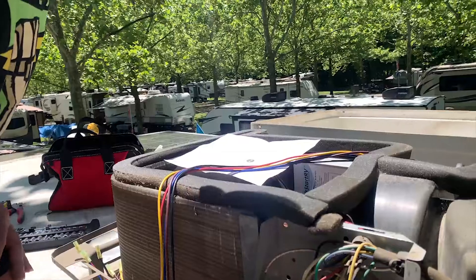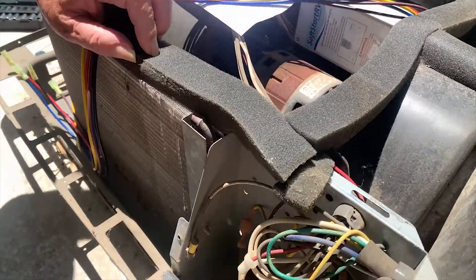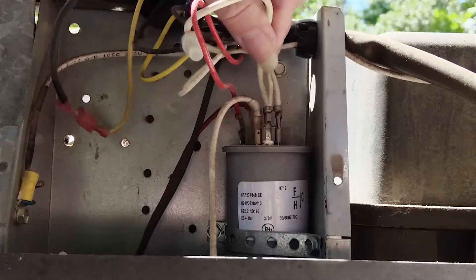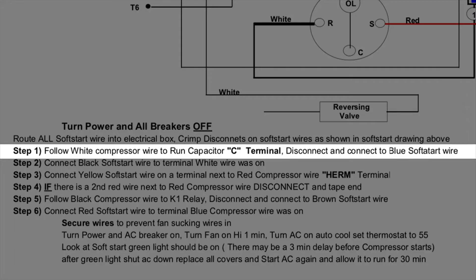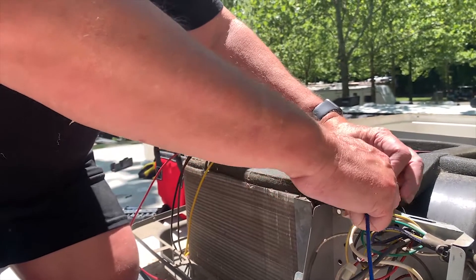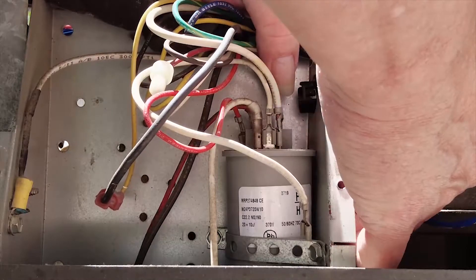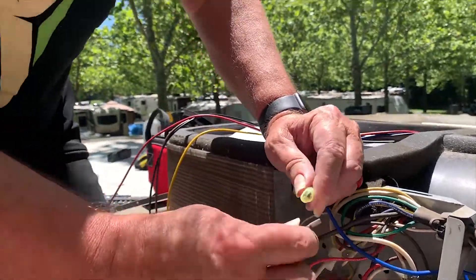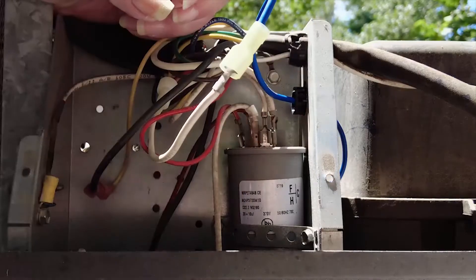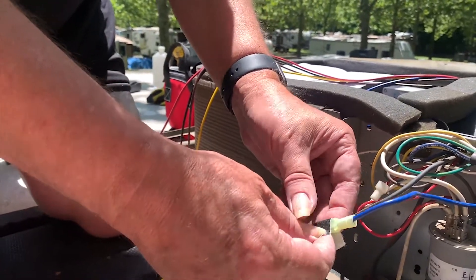Follow the white compressor wire — these are the compressor wires, so this is the white one. Step one: follow white compressor wire, run capacitor C terminal, disconnect and connect to blue soft start wire. So this is the blue one. The blue wire connects to the white wire we just disconnected.